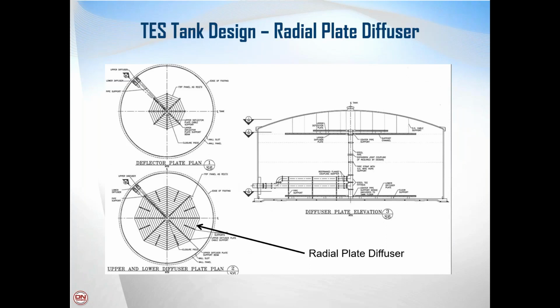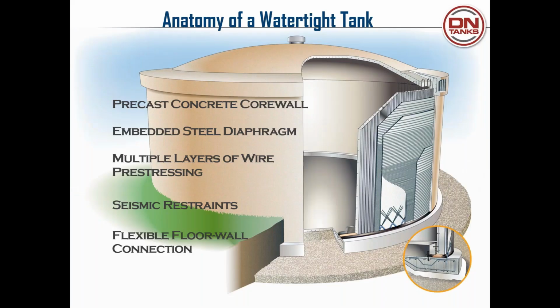We also can provide a radial plate type diffuser system in the tank, with similar principles where we want to slow down that flow, stratify that chill water in the tank. So we're capable of designing either type of those diffuser systems within our tank, and typically we decide which is the most beneficial based on the flow rates going through the tank.